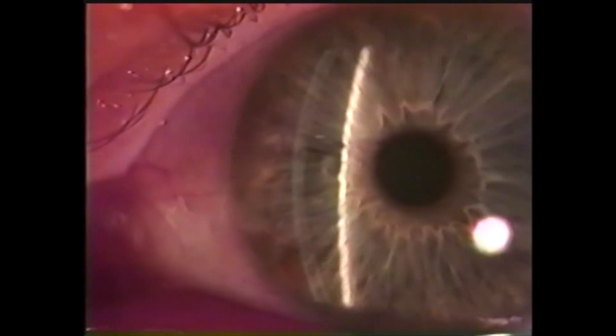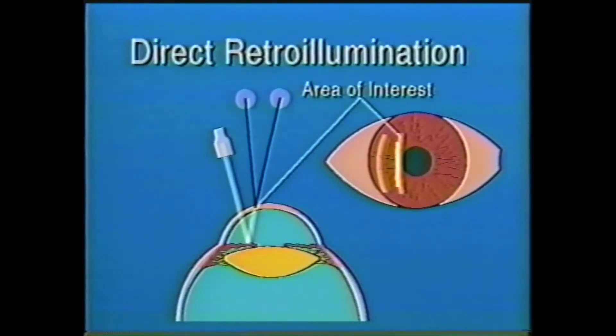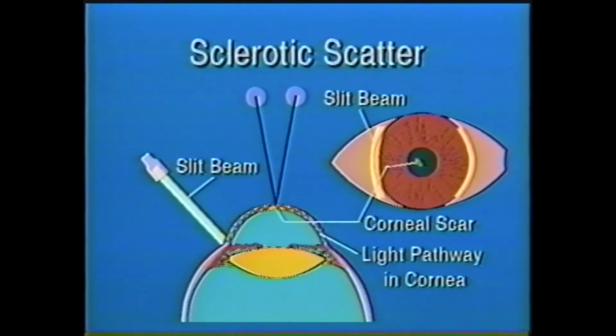In summary, there are six types of slit lamp illumination that can make your biomicroscopy of the anterior segment more revealing and rewarding: diffuse, focal, proximal, direct and indirect retro illumination, specular reflection, and finally sclerotic scatter. It is the fine adjustments of the angle of the lamp arm and the joystick that reveal the subtle details. Slit lamp biomicroscopy is a dynamic exam.